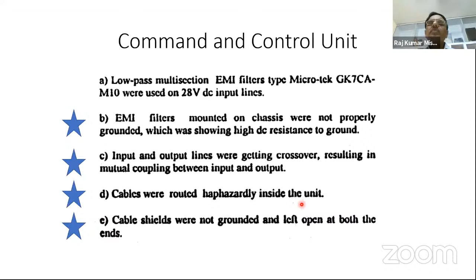So at design time, one should be very mature. Cables were routed haphazardly inside the unit. You have to properly lay out the cables, because the cable shields were not grounded and were left open at both ends. This I myself have seen in many EUTs, the systems which came for testing. This problem I have noted myself.